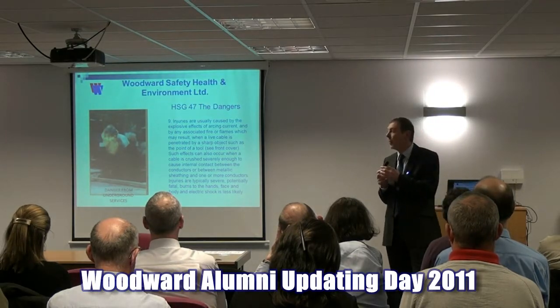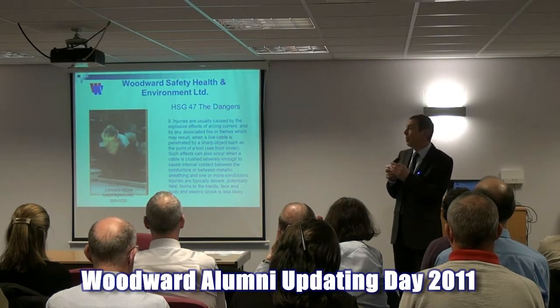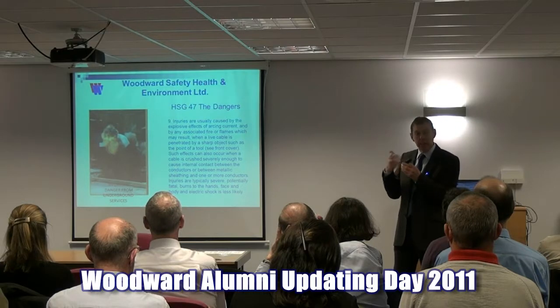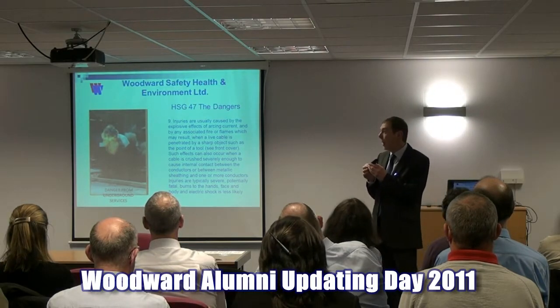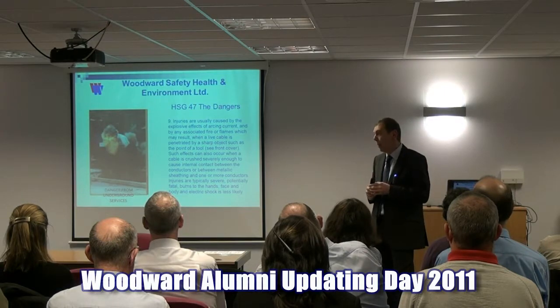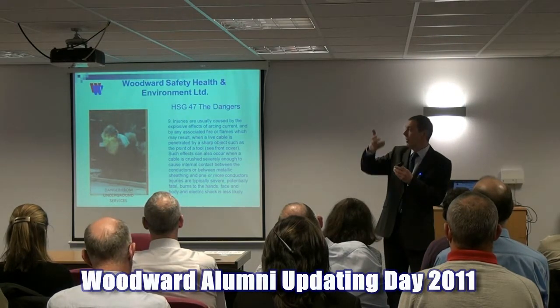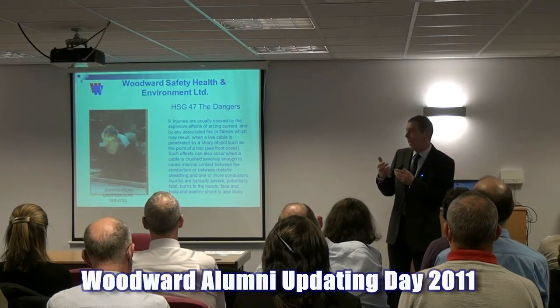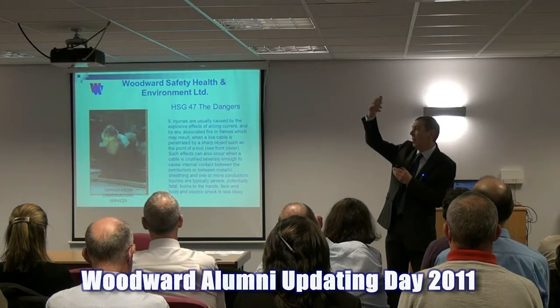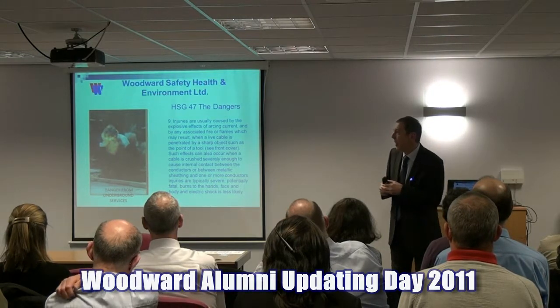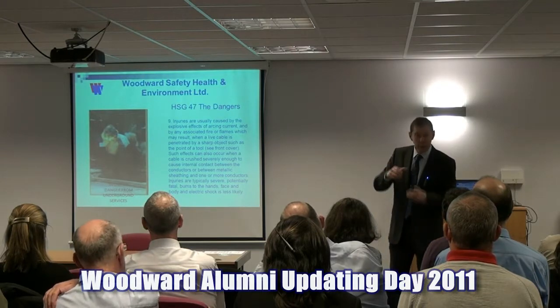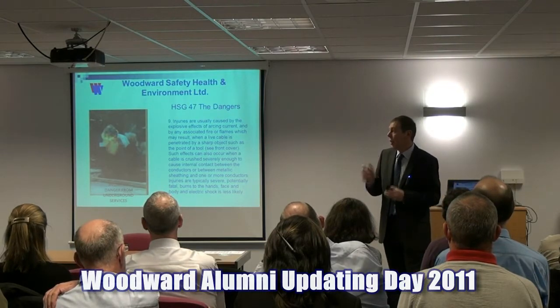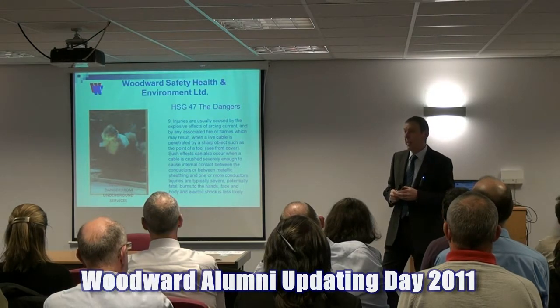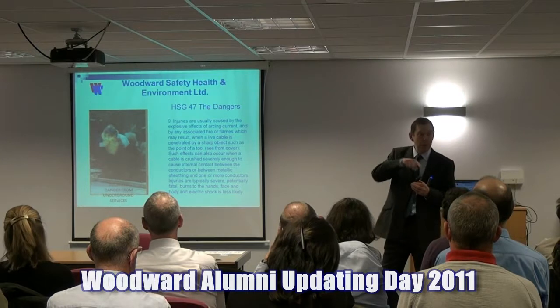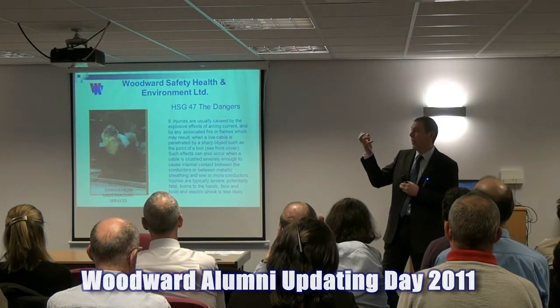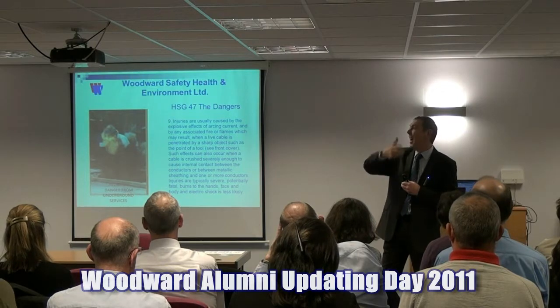The screwdriver heats up, then melts. It moves on to the next level because the current is still flowing, and the screwdriver and the contacts it's across start to burn. The burning causes heat to rise, and the rise of heat takes metal particles up into the cloud - it's called a plasma. If the technician has the foresight to try and get the short circuit out of the way, get the spade out of the way, the current still flows. What they now know is the short circuit can be removed, but the current is still flowing courtesy of the metal particles now suspended in the atmosphere.